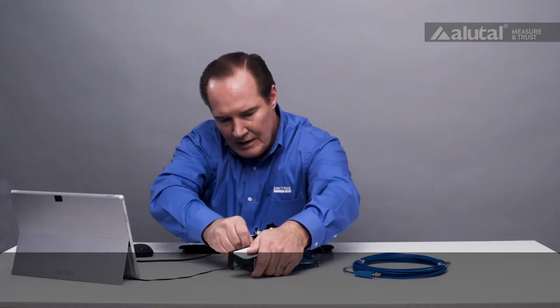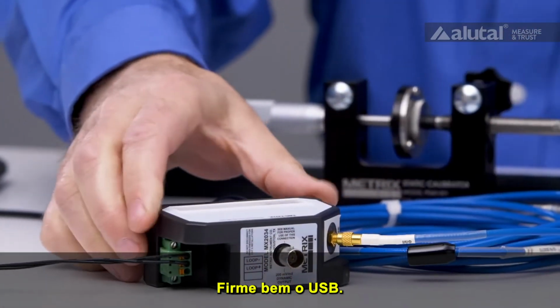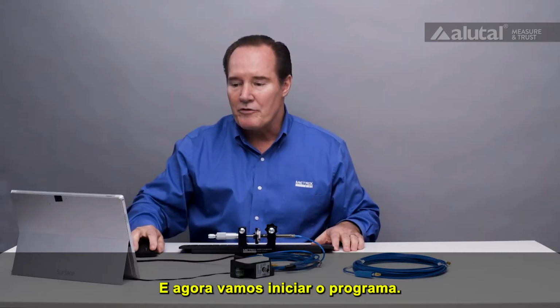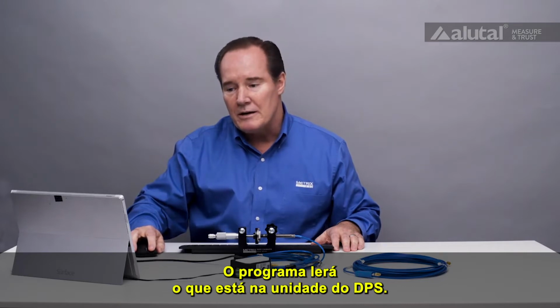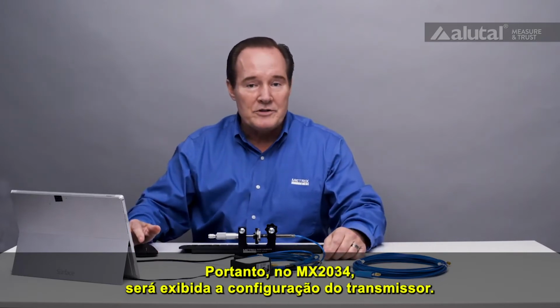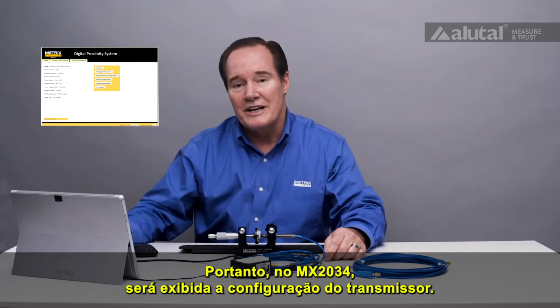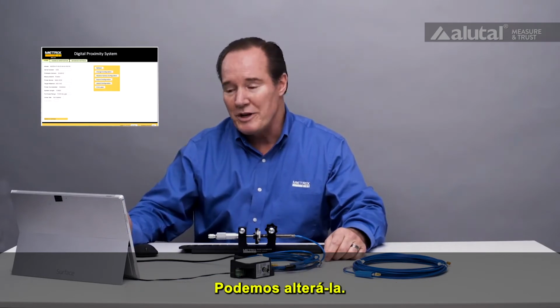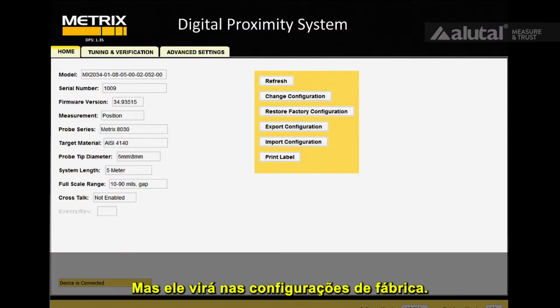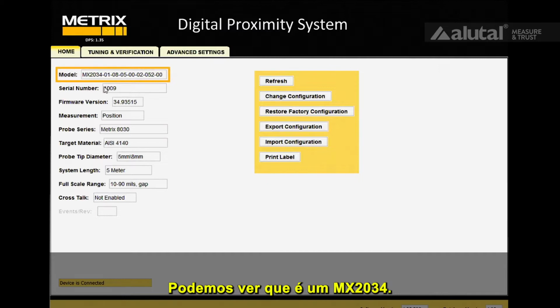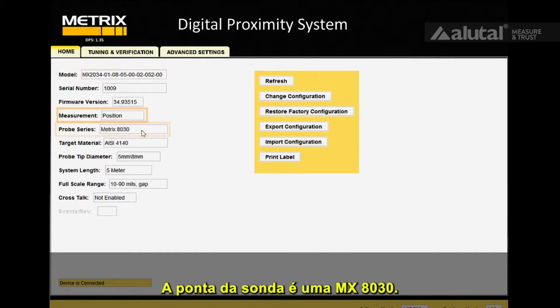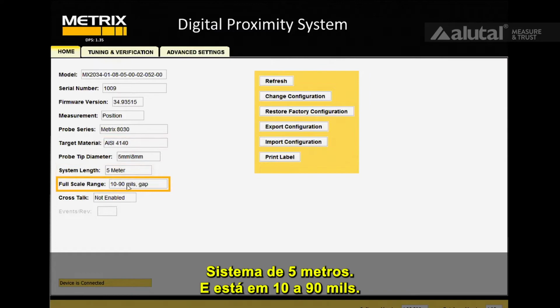All right, so I'm going to go ahead and connect to it. And you want to press that USB in there firmly. And then we'll go ahead and start the software. Now the software will actually read what's on the DPS unit. So on the MX2034, it'll bring in its transmitter configuration, which we can change, but whatever's built from the factory, that's what it comes in on. So we can see here that it's an MX2034, its position, it's a Metrix 8030 probe tip, 4140 steel, 5-meter system, and it's presently on 10 to 90 mils.